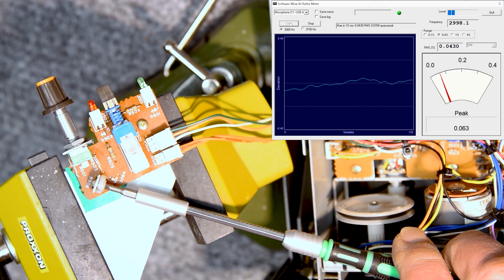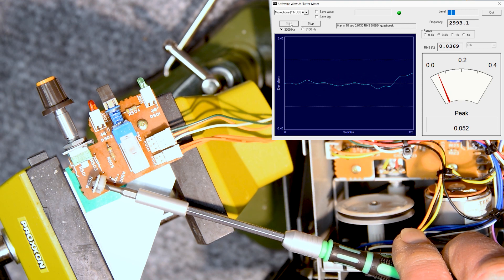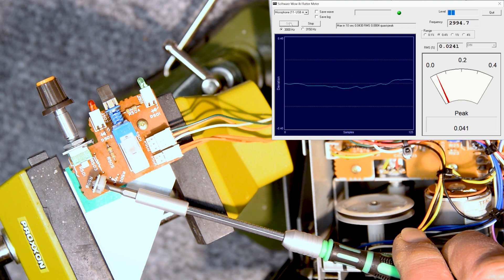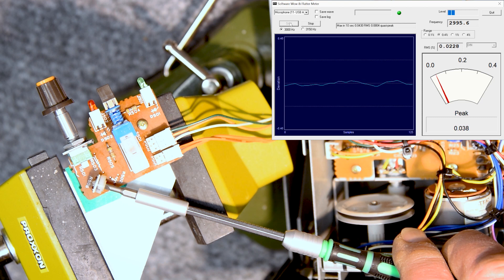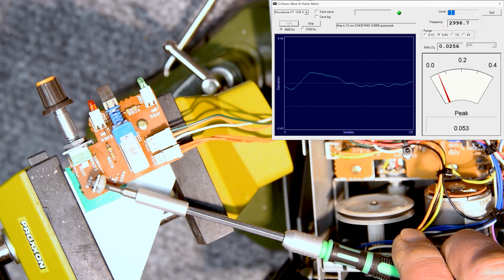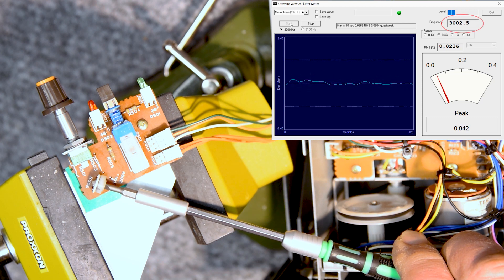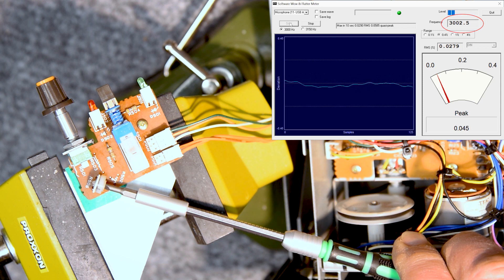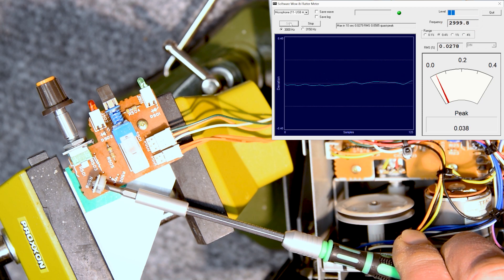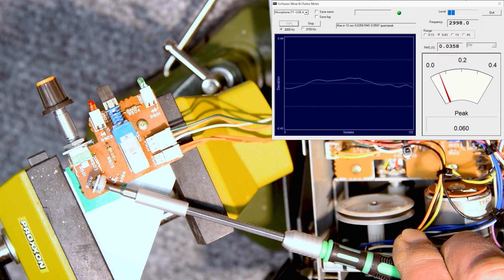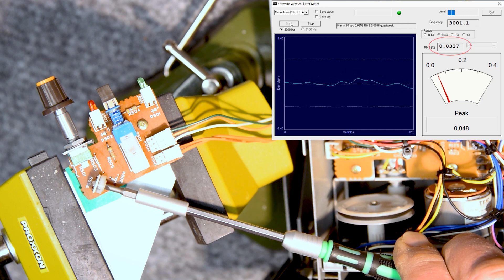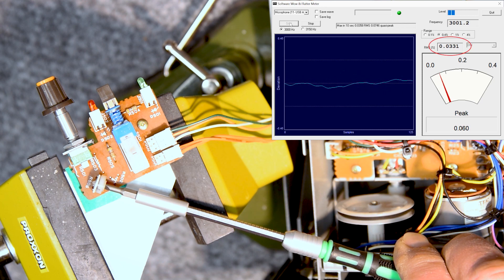Dial this into about 3000 hertz, looking at the frequency number there on the upper right hand. And then also paying attention to the wow and flutter, the RMS number there, just looking for stability.